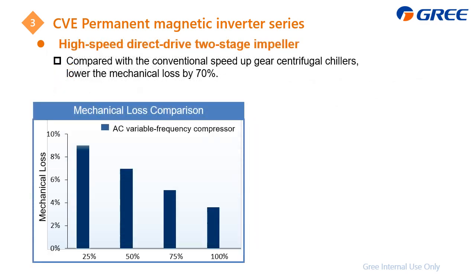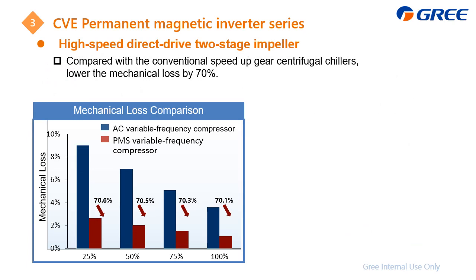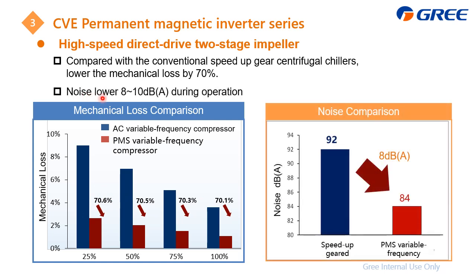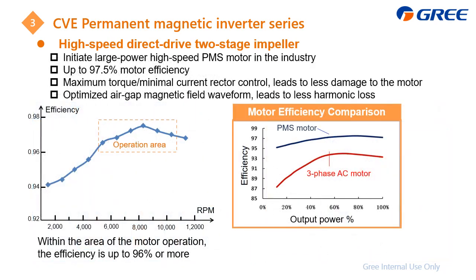Next is the benefit we can get from changing the RPM of the compressor. Here, under the AHRI test condition, is the mechanical loss comparison. This one is the AC motor, which is the on-off CE series, and this one is the CVE inverter, which can change the RPM. We can save up to 70% of the mechanical loss just due to having no speed up gear and direct drive. For the noise, it can be about 8 decibels lower compared with the speed up gear CE series. This is the benefit we can get if we adopt this CVE series.